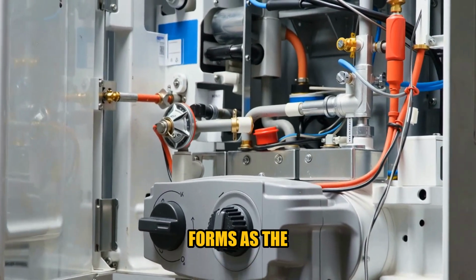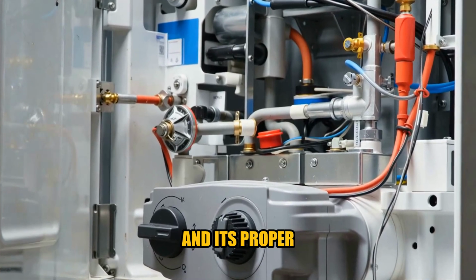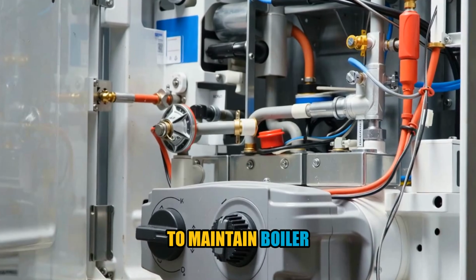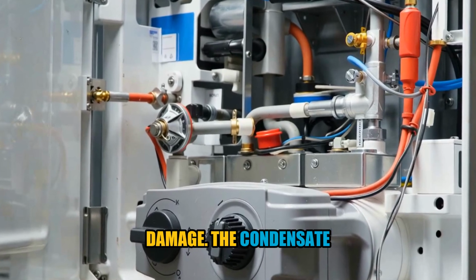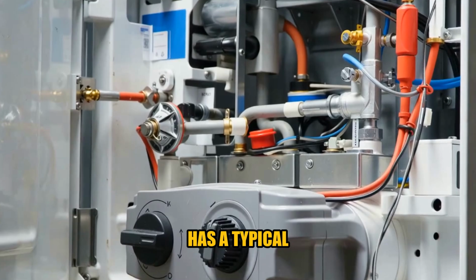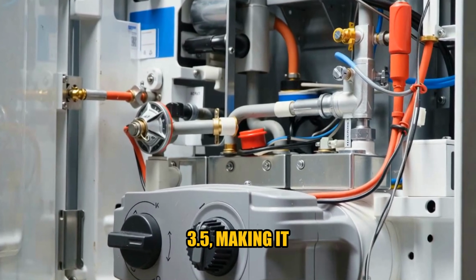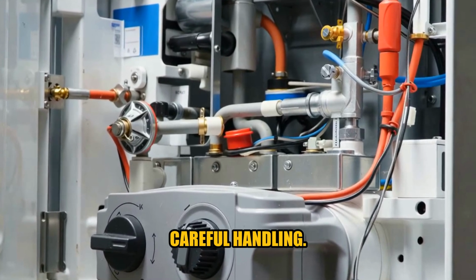The condensate forms as the flue gases cool, and its proper disposal is essential to maintain boiler efficiency and prevent damage. The condensate has a typical pH level of 3.5, making it acidic and requiring careful handling.